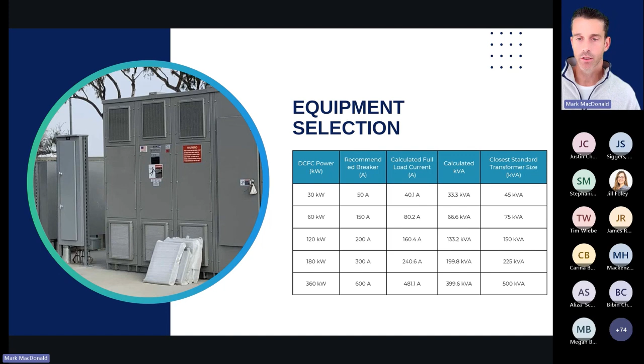If we go up to 360 kilowatts, you're talking 500 kVA. The most common, of course, is the 180 kilowatt charger that we sell, so you're looking at a 225 kVA supply transformer. And then for breakers, we have the technical spec requirements, but at 80% rated, you're looking at a 300 amp breaker on that 180 kilowatt service.